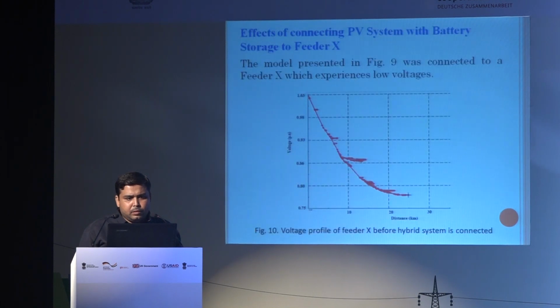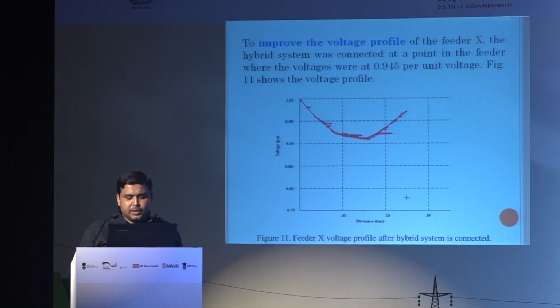This slide mainly shows the effect of connecting a PV system with battery storage to feeder X. Earlier, the figure shows the voltage profile of feeder X before the hybrid system was connected, continuously going down, which could make the system unstable. So to improve the voltage profile of feeder X, the hybrid system was connected at a point in the feeder where the voltage was at 0.945 per unit.